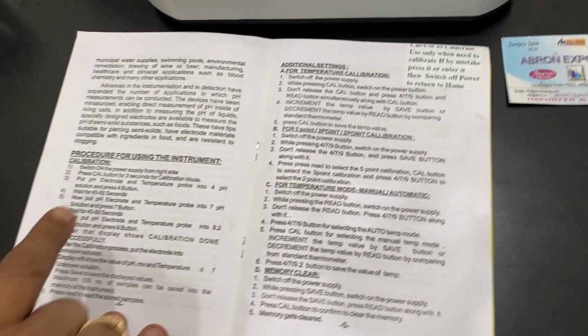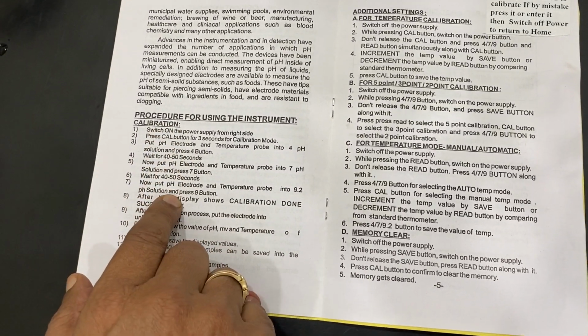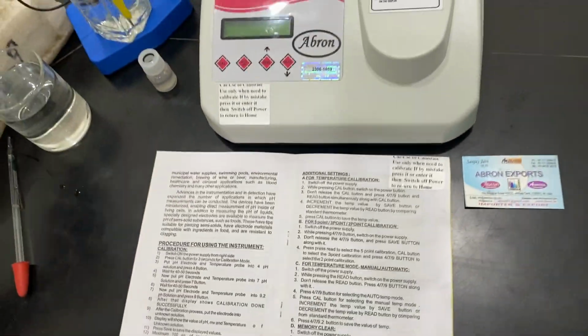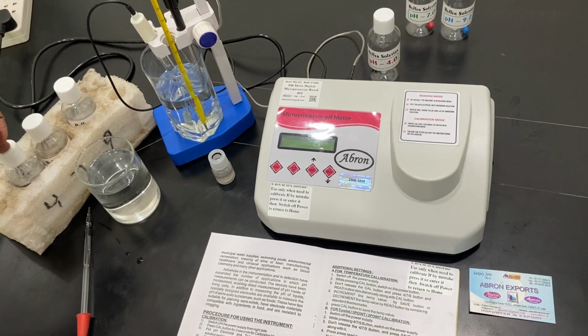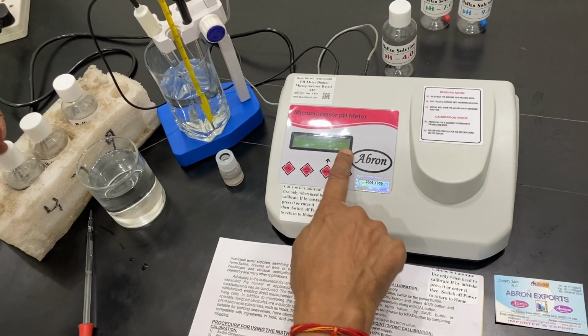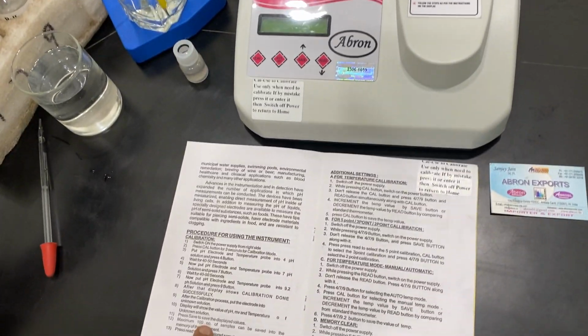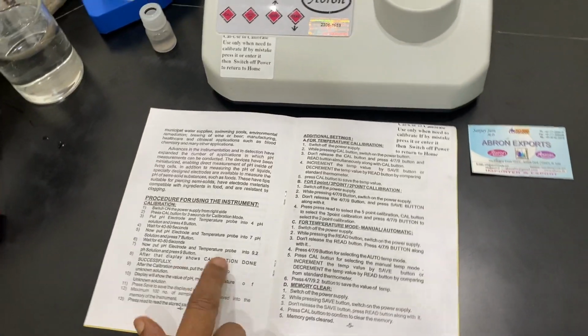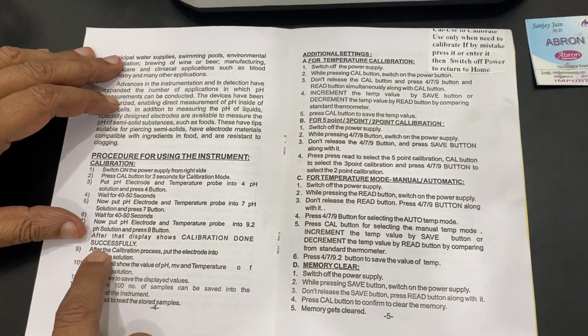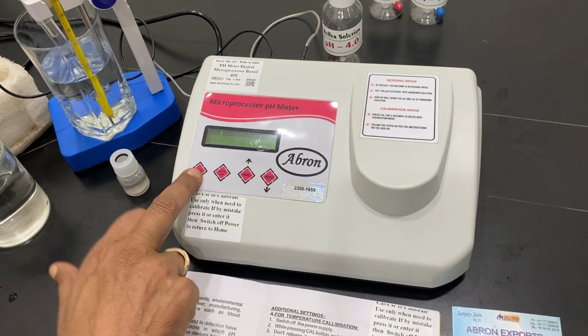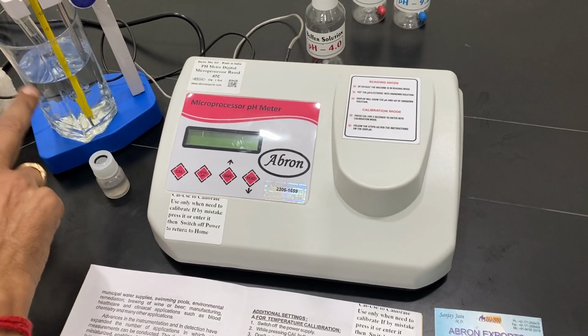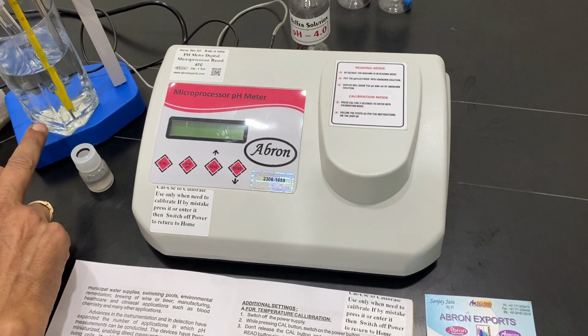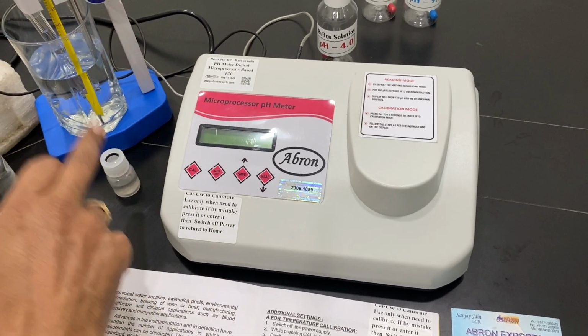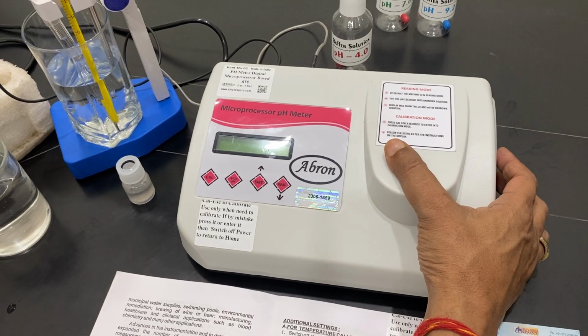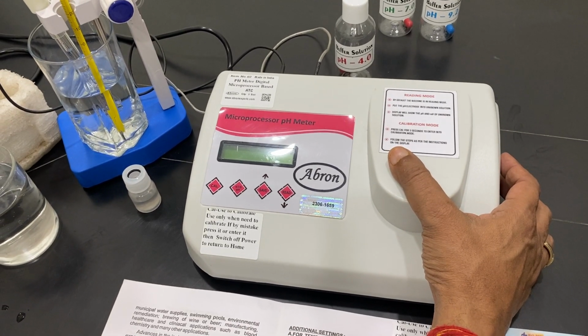Next, this is the calibration procedure that has been written. You enter that mode, then put the electrode in pH 4 when it says enter pH 4. Then pH 7, when it says enter that. Then pH 9, and it enters. Only then is calibration done successfully. Then you can start. Once you accidentally calibrate and keep it in water, the solution will be taken as pH 4, and it will show a minimum of 4 pH. So better avoid calibration unless it is very much required.